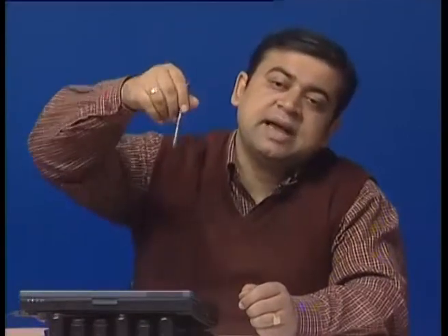Similarly, the amount of time that is needed to hold the drop in the 50 degrees area is essentially the ramp down time to the 50 degrees plus the amount of time it would take for the sample to be present in the annealing step. Similarly the same goes for the extension step. So you have to design effectively the velocity of this droplet in a manner so that length, which is equal to velocity times time, would be able to give sufficient time for the denaturation, the annealing and the extension process of a PCR to occur in an easier manner.